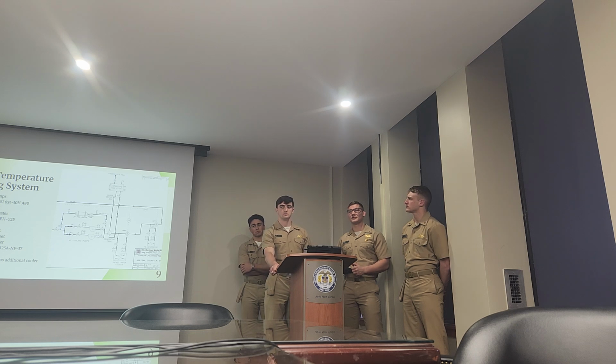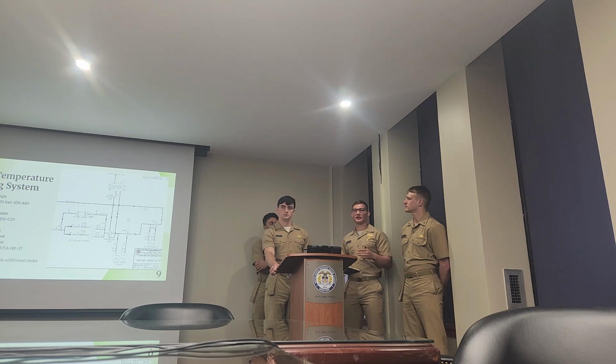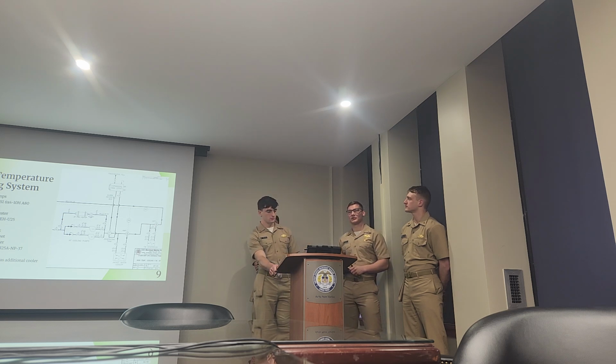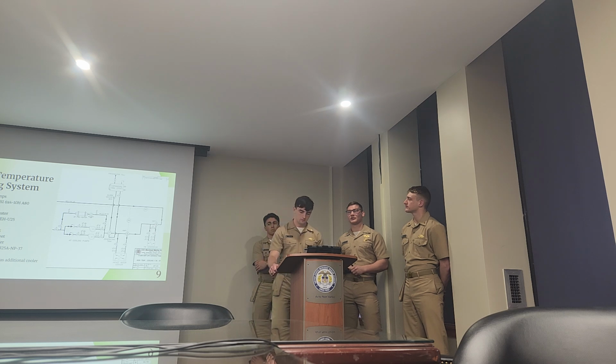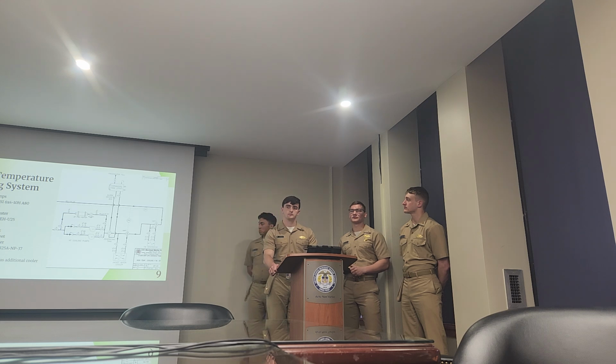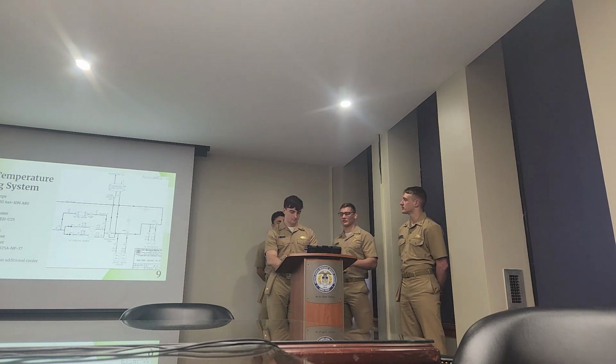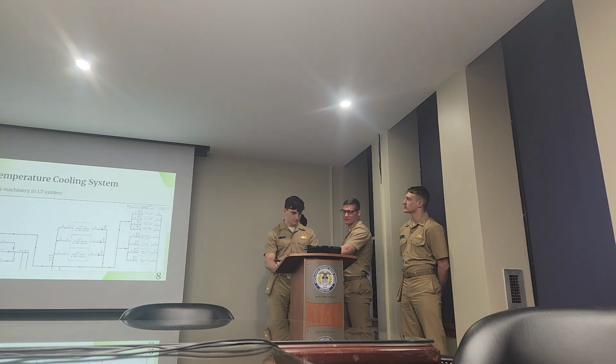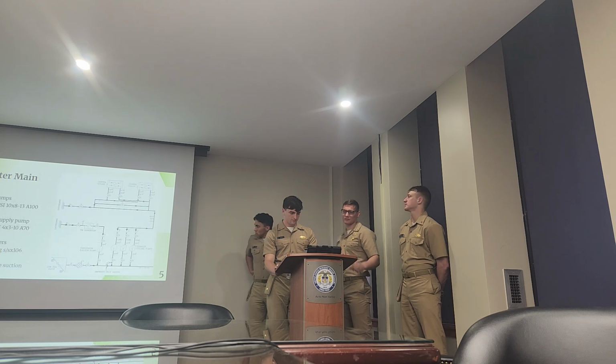Well, that's what I did. I found the motor in the catalog. But then you should write that on there, as far as here's the motor that we want, or show me the calculation that we had a 57 horsepower, but we're picking a 60 horsepower or 75 horsepower to fill the need for this particular pump. So again, I don't think that there's a 57, and for that matter, you have all these different pump sizes that they need to be rounded up.